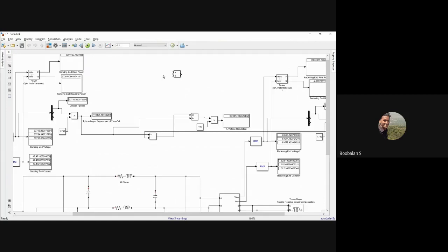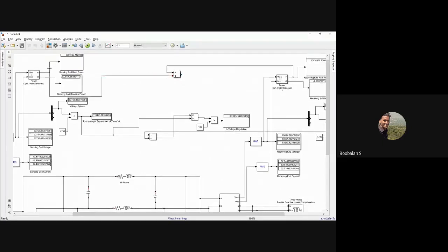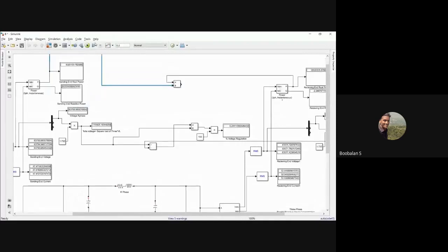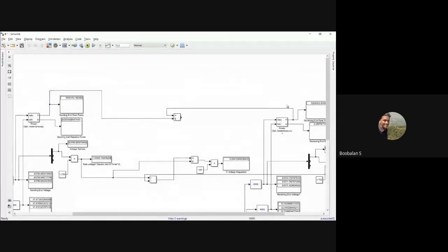This is what my power delivered at my sending end, sorry, receiving end, right? So divided by sending end. Simply I'm just using a drag, right? So power at my receiving end divided by power at sending end. We need a multiplier, one second, times 100, right? So this one times 100. This will give you my transmission line efficiency.